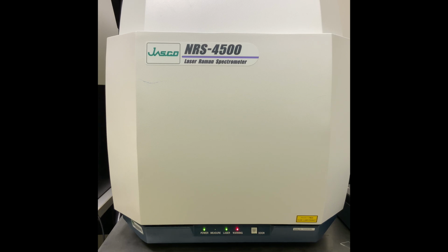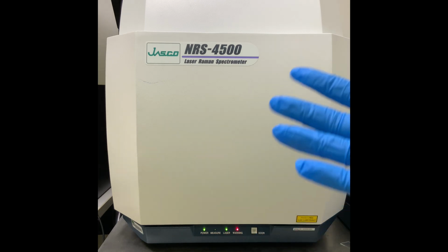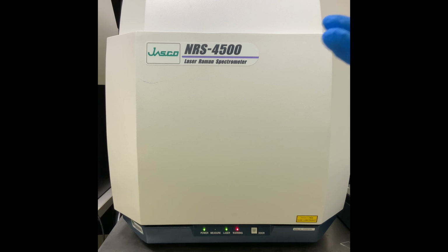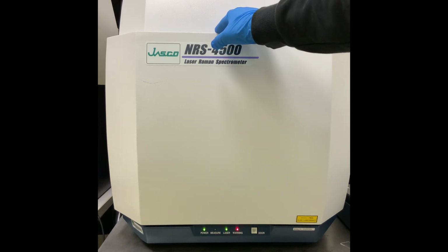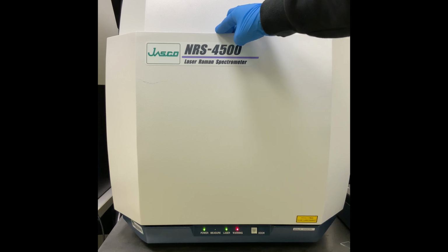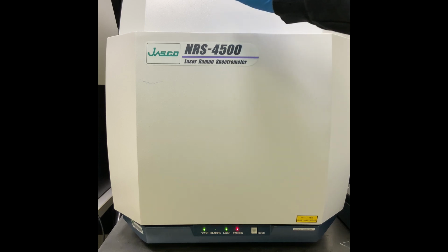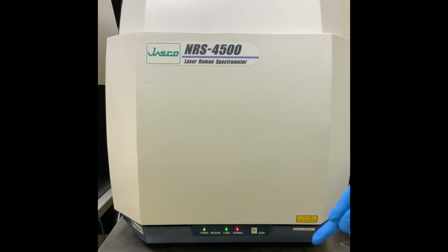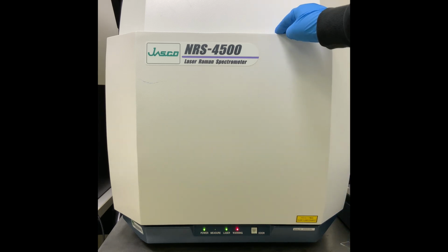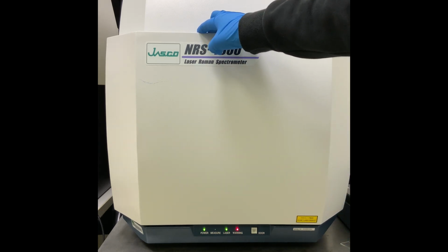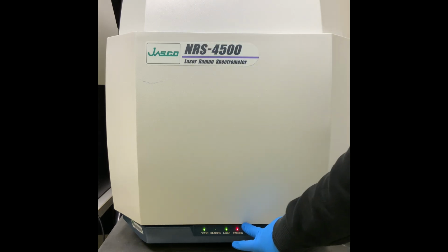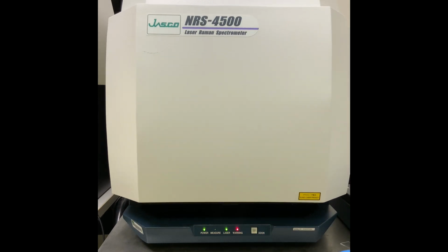Now when you're closing the door for calibration, once the laser is on, you need to hear a click to know if the laser comes on. Now due to wear and tear with the spectrometer itself, the door might not close completely, so the laser would not come on. And to close it, you just press gently on it, and that click there signifies that the laser is on. If you hear a double click like this, the laser would come off. So just gently press on it again. And if it clicks on and off, open the door and close it again.